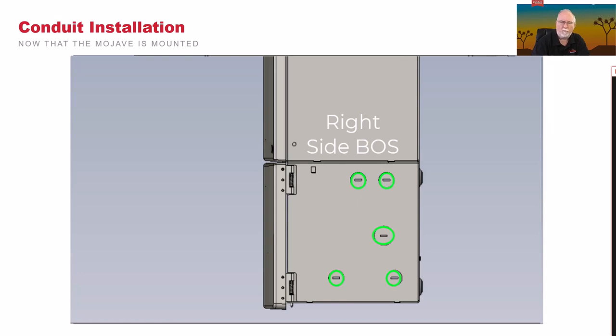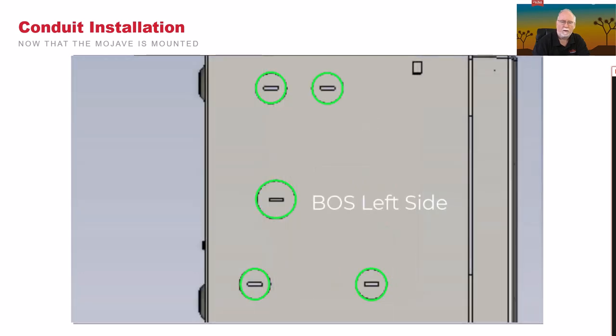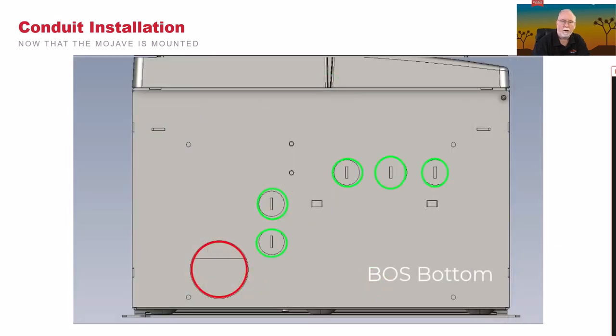There are 4 knockouts that are 3/4 inches in diameter, designed to fit a 1/2 inch conduit, 1 knockout that's 1 inch, designed to fit a 3/4 inch conduit. Now, to be honest, most of the time when I've done this, effectively you do the knockout and then you use a punch out tool to enlarge it as needed. And again, that's the right side. This is the left side, again showing the 4 3/4 inch knockouts, the 1 inch knockout. On the bottom, very similar. The items highlighted in green are for AC connections.